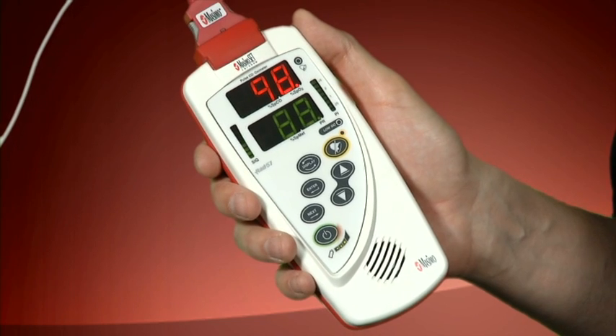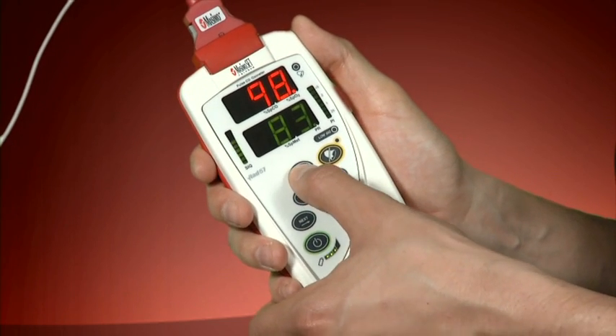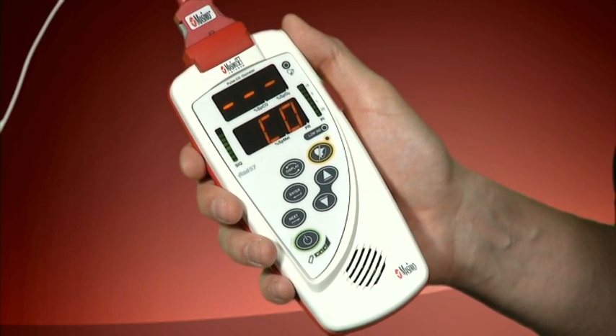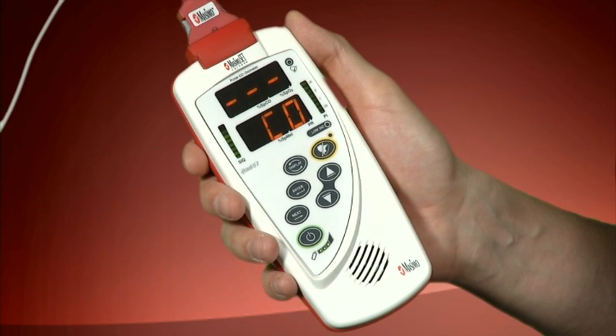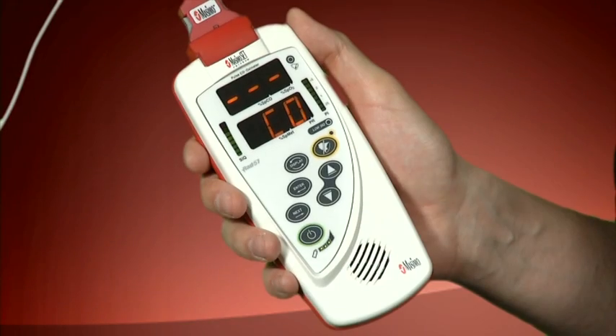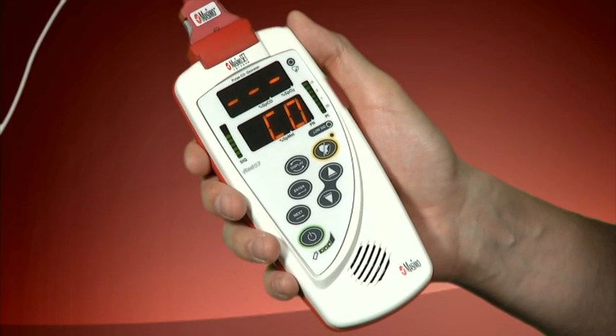Press the display button to change the numeric display from the SpO2 pulse rate screen to the SpCO and SpMet screen. It may take a few extra seconds, even after the SpO2 and pulse rate values have been displayed, for the SpCO and SpMet to calculate. You will see dashed lines while these measurements are being calculated. Rainbow parameters such as SpCO and SpMet are always displayed in orange. The SpCO reading will be on top.